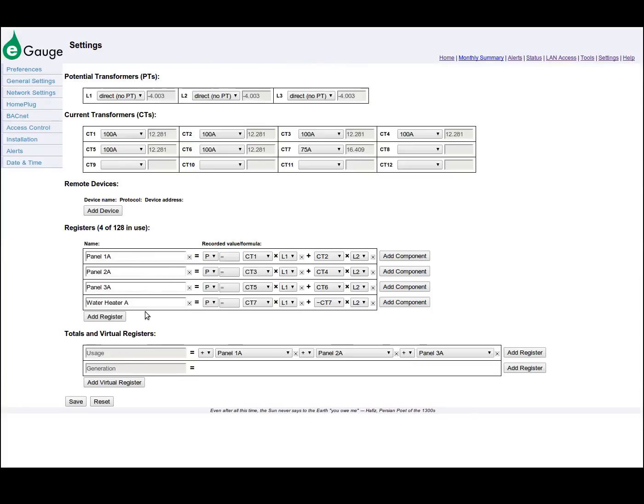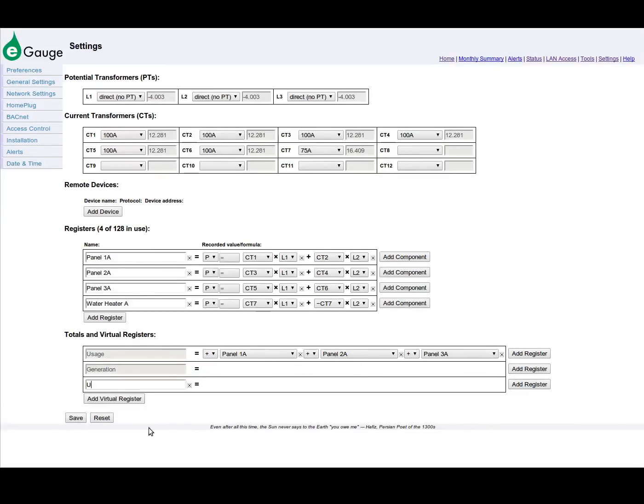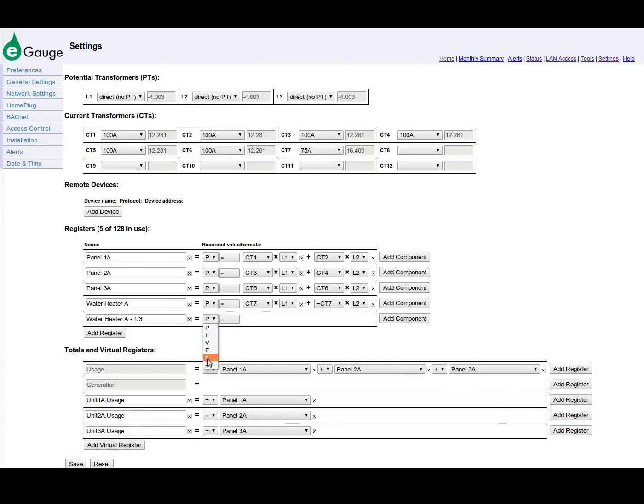This E-Gauge is monitoring panel 1A, panel 2A, panel 3A, and water heater A. Each tenant's unit has their own panel. The main usage register is the combination of all three panels. Next, we define views for the usage of Unit 1A, Unit 2A, and Unit 3A as such.